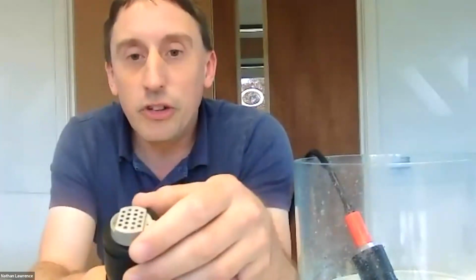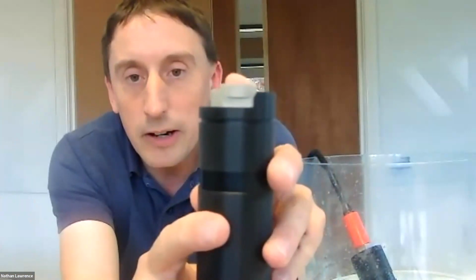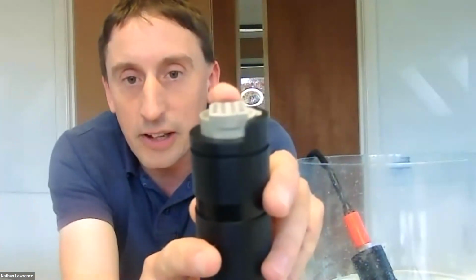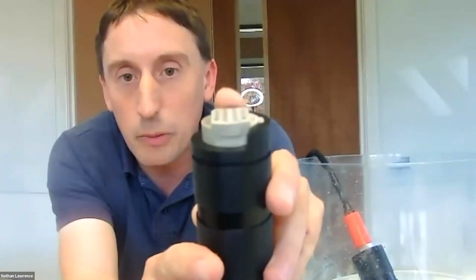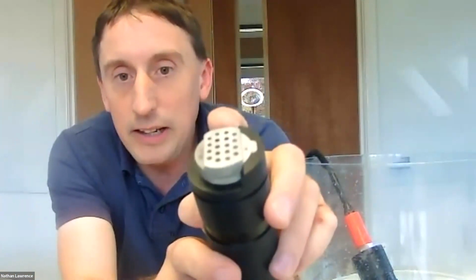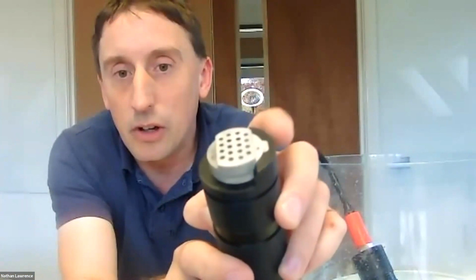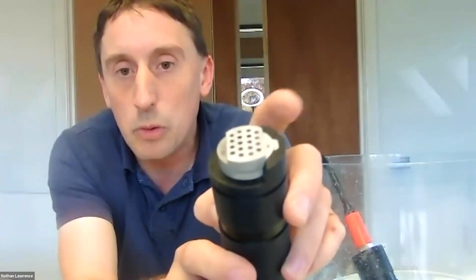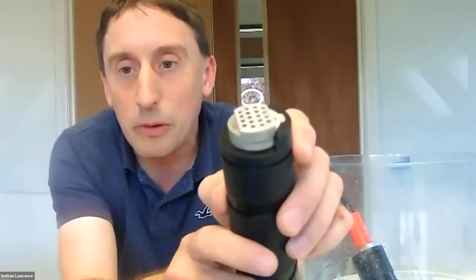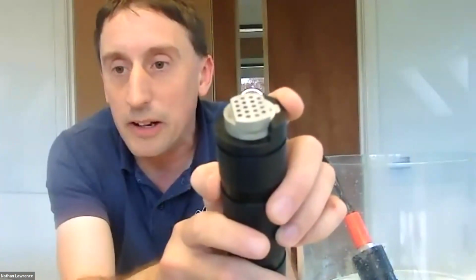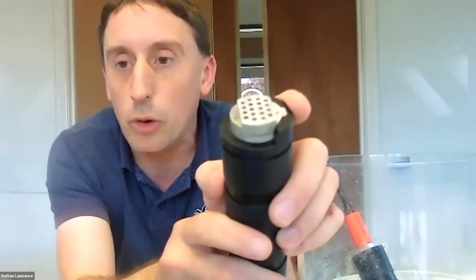If we look at the transducer itself, I'm not sure if the definition will come out too well, but we only ever abrade the top face of the sensor and not these 2 side parts here. We only ever abrade the top face. These are our pH sensing elements. On the other sides are our thermocouple, reference elements, and reference checking elements, and they don't require any abrasion. They're perfectly fine for long lifetime deployments.